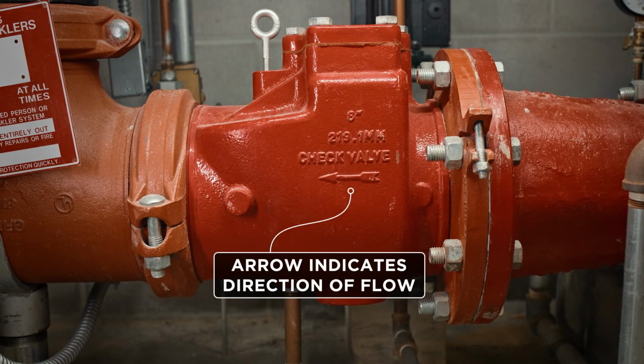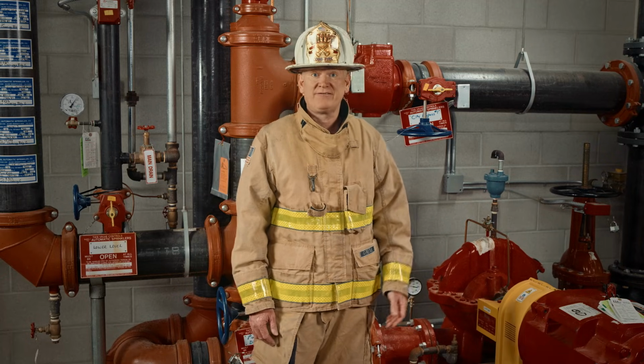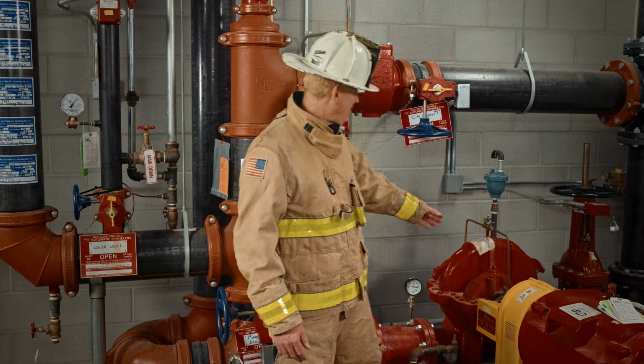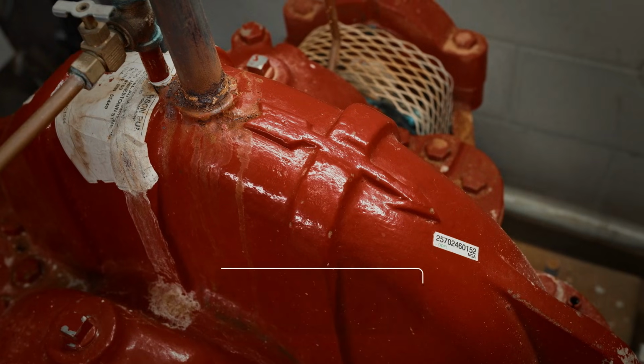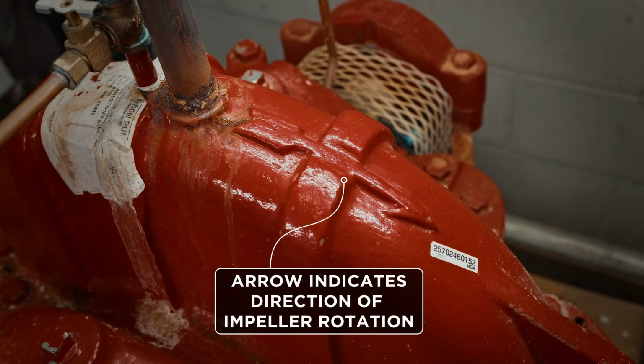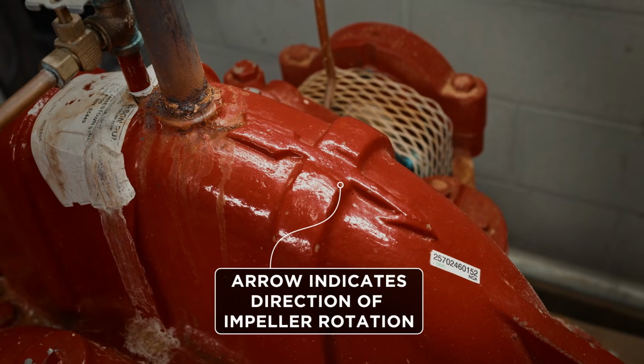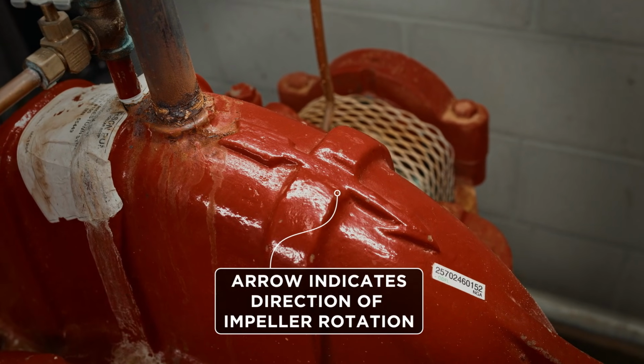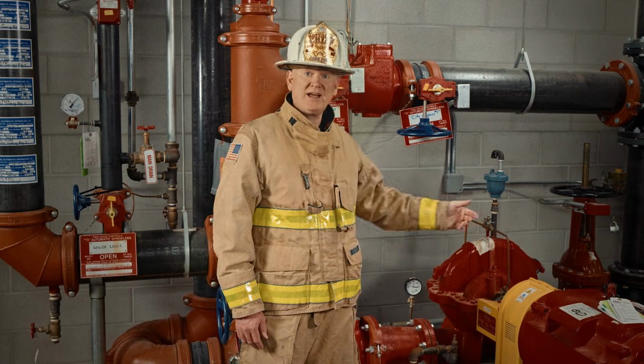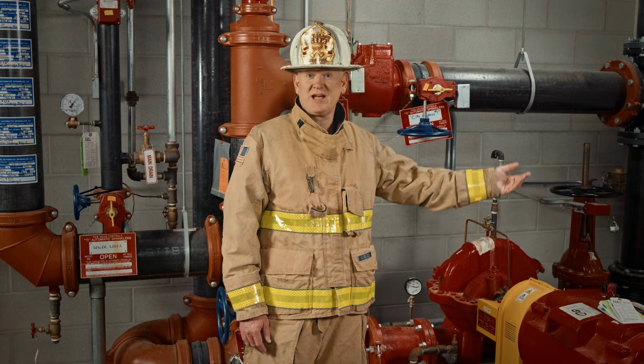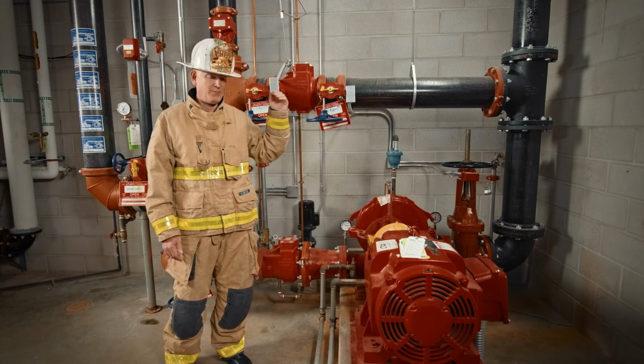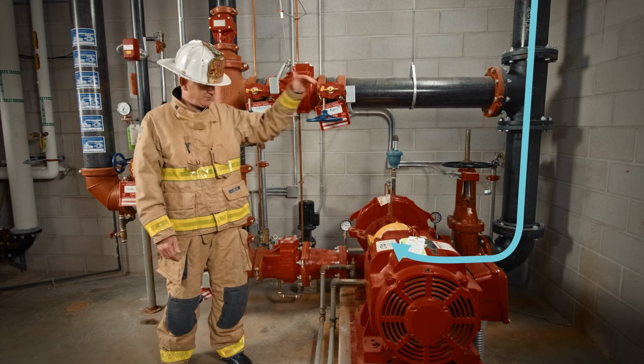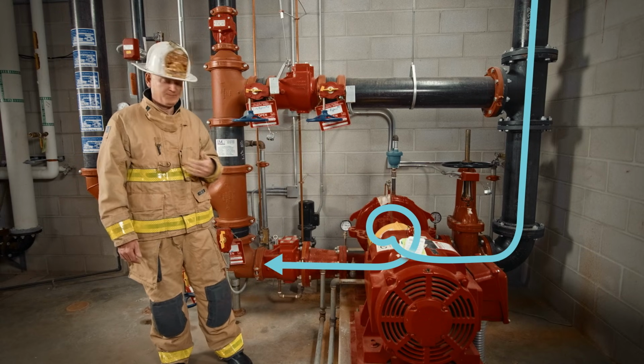Another way that you can identify the direction of that flow on this type of fire pump, there's an arrow in the pump casing itself. That arrow indicates the spin of the impeller in that pump casing. Typically, that spin arrow will point towards the supply side or the municipal side of the fire pump, thereby indicating that the water is going through the pump and out towards me.